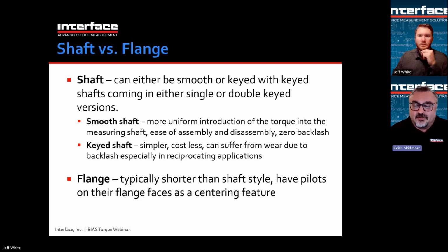The problem is if you use an interference fit with a keyed hub on a keyed transducer shaft, it becomes very difficult to remove the coupling hub without damaging the transducer shaft. In fact, the transducer shaft may very well be damaged installing the hub, and then when you pull it off, it damages it further. And so, torque sensors are expensive. They're not intended to be consumed, and so it's best not to use couplings that damage the shafts. Also, if you can't get the couplings back off, it's very difficult to have the torque sensor calibrated.